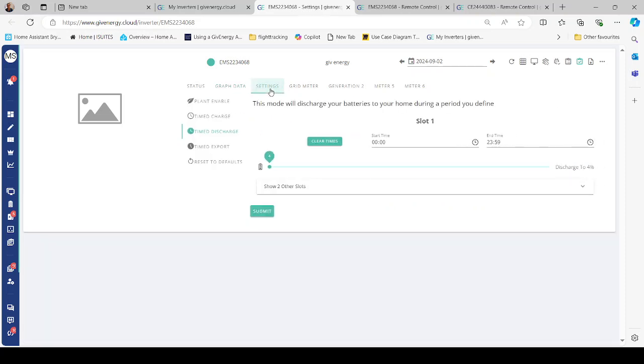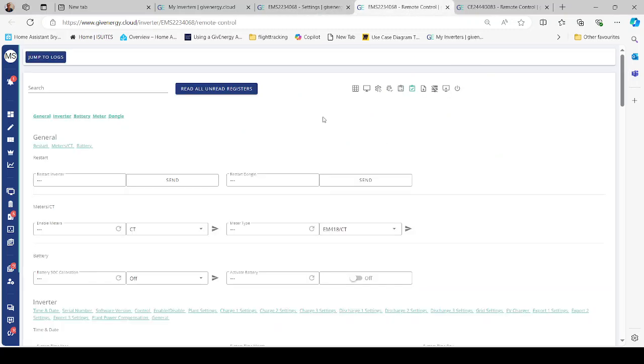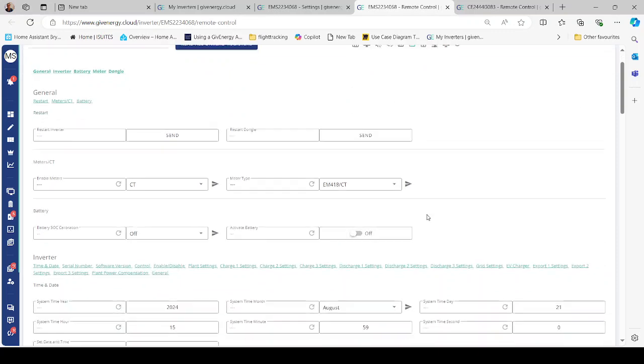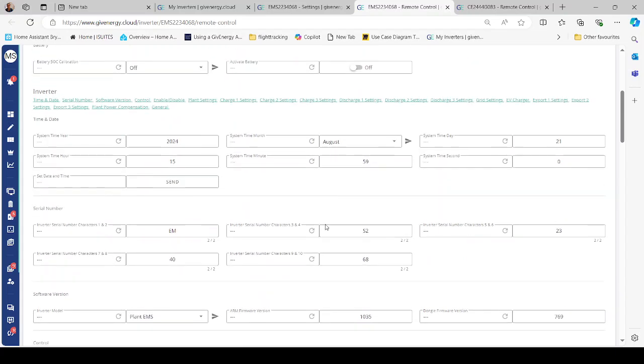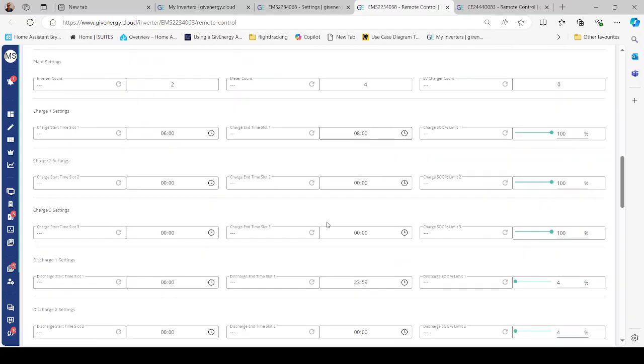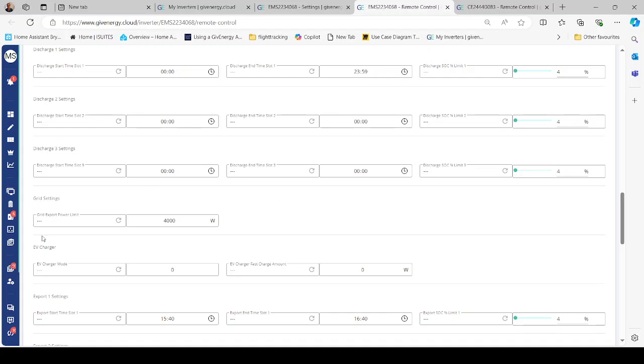Well, that was settings. Settings are relatively simple to do. What to look for EMS wise, if it's not exporting, it's probably because an export slot has not been set. If we look at the remote control for the EMS and we scroll down, in between two of the slots is the export limit. And that's how much it will allow to export. If that is set to 0, it won't export. I get a copy of the customer's DNO agreement for how much they're allowed to export and then set it in there in watts. Not kilowatts, but watts.